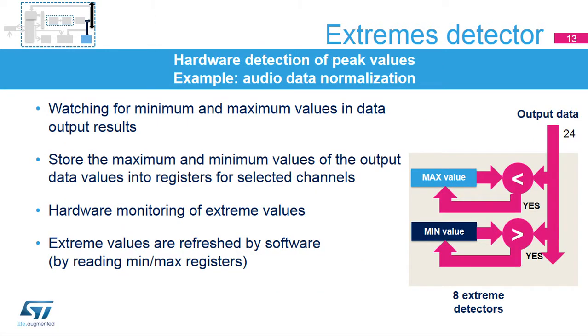The extremes detector monitors output results and stores the extreme values into minimum and maximum registers, as well as the associated channel number. Monitoring of data for extremes is only performed on selected channels to ensure that channels do not mix different input levels. Stored extreme values are refreshed each time the values are read in the register.